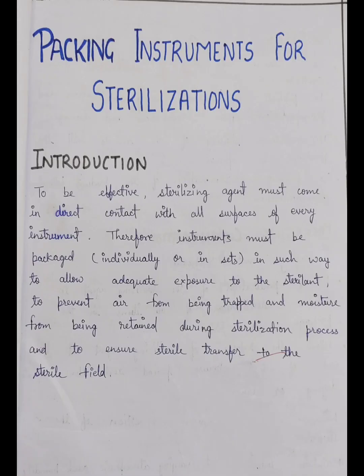After that we start with the introduction. Effective sterilization: the sterilizing agent must come in direct contact with all the surfaces of every instrument. Therefore the instrument must be packed individually or in sets to allow adequate exposure to the sterilant, to prevent air from being trapped and moisture from being retained during the sterilization process, and to ensure sterile transfer to the sterile field.